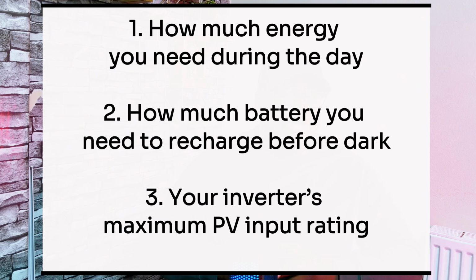The solar array, the number of solar panels on your roof, is sized separately based on these factors: one, how much energy you need during the day; two, how much battery you need to recharge before sunset; three, your inverter's maximum PV input rating — the total solar energy your inverter can handle from the panels.